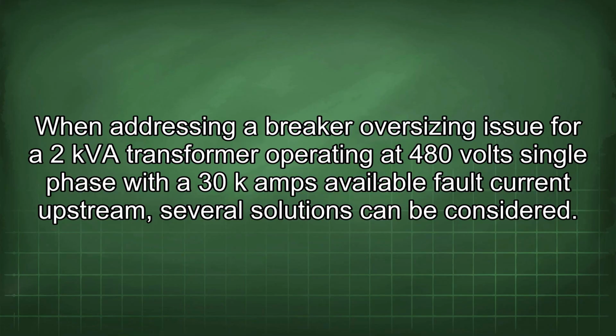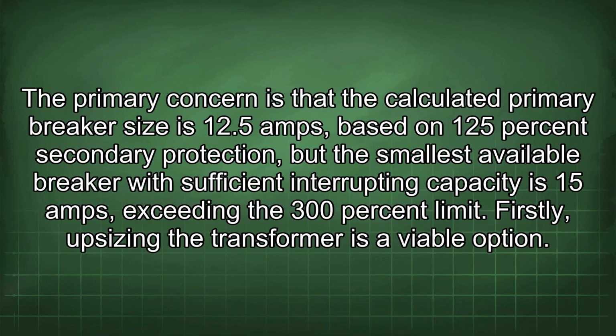When addressing a breaker oversizing issue for a 2 kVA transformer operating at 480 volt single phase with a 30 kA available fault current upstream, several solutions can be considered. The primary concern is that the calculated primary breaker size is 12.5 amps based on 125% secondary protection, but the smallest available breaker with sufficient interrupting capacity is 15 amps, exceeding the 300% limit.